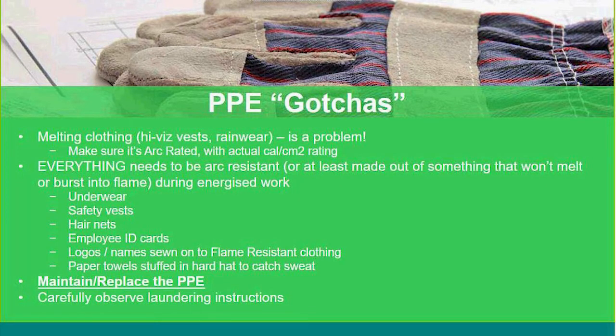The trouble is, everything needs to be arc resistant. We do see people where they have particular PPE gear, and they might completely overwrite the arc flash calorific rating by putting a non-standard high-vis vest over the top of it. So hairnets, employee ID cards, logos, names, any arc flash clothing really should only be washed in water, nothing else. You can't use fabric conditioner because it contains animal fats, and those animal fats reduce its ability to not be flammable. So you have to take lots of precautions around the laundering of the PPE equipment.